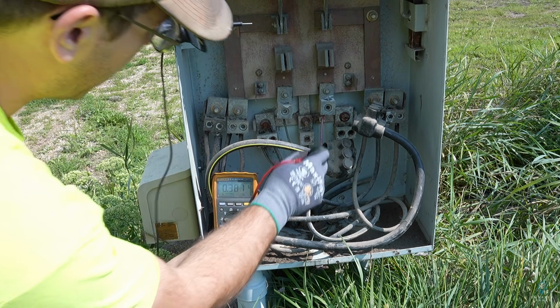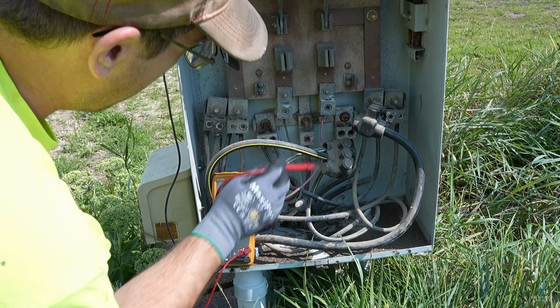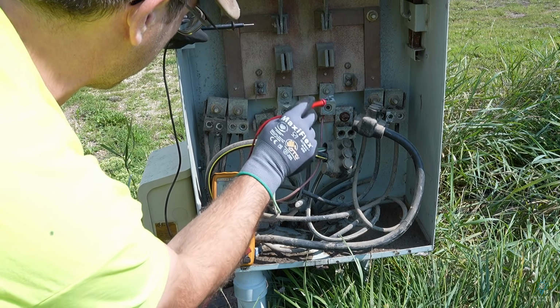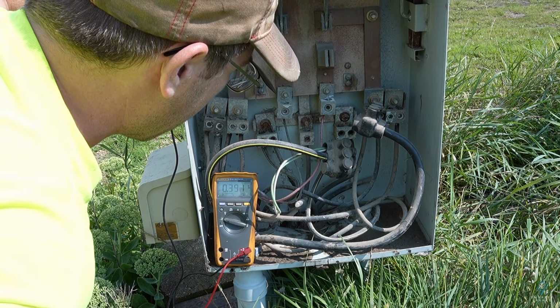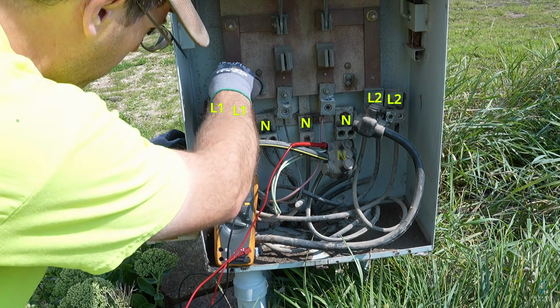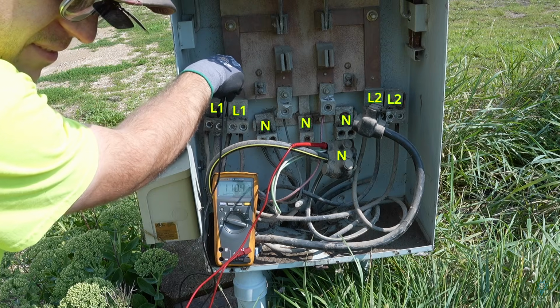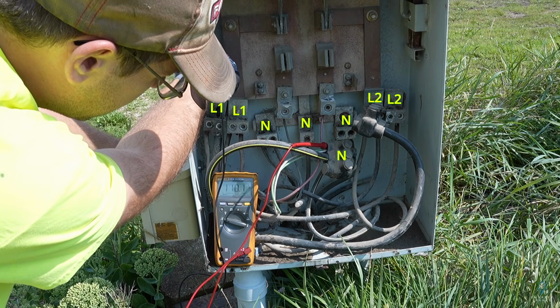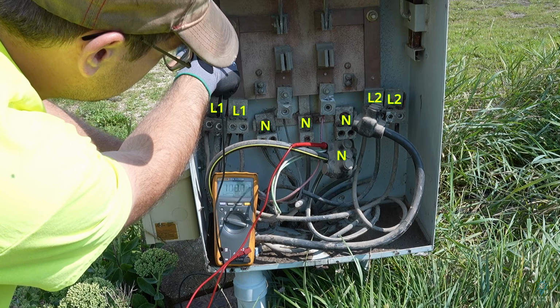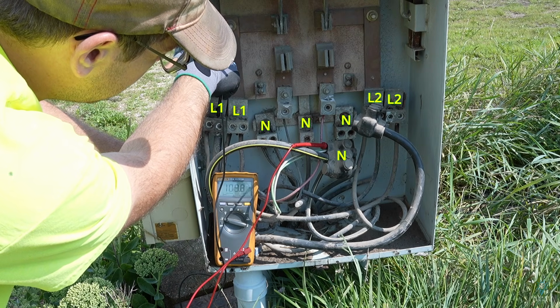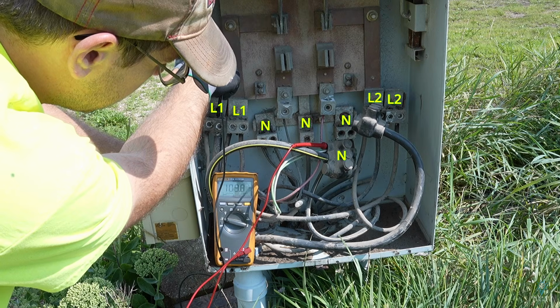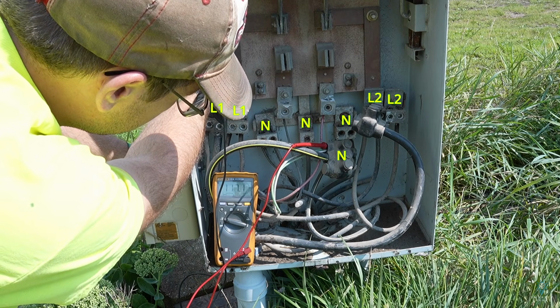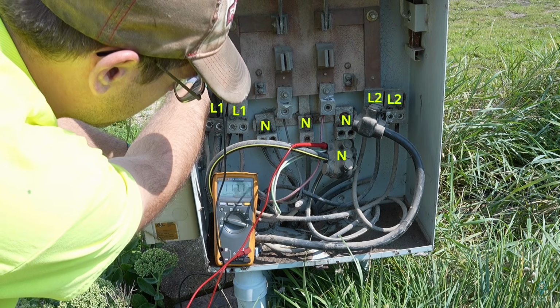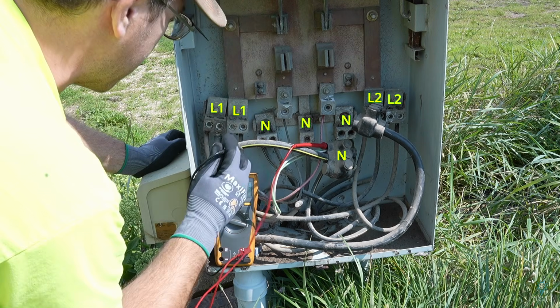All right, well, let's see if we can observe this voltage drop and figure out exactly where. My guess is it's that set of lugs in the very back there. That is my guess. So if we go to line 1 here, yeah, look at that. 109 volts, 110 to neutral. And there we go, 117. So we're seeing those exact same fluctuations at this lug right here.